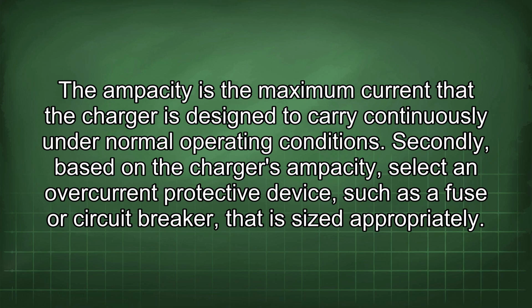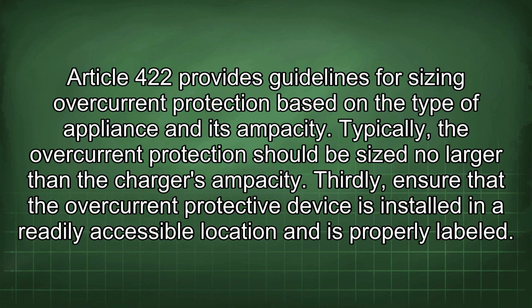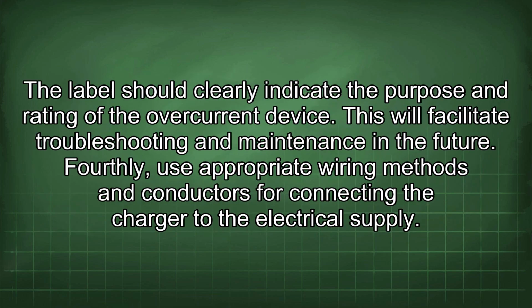Secondly, based on the charger's ampacity, select an overcurrent protective device such as a fuse or circuit breaker that is sized appropriately. Article 422 provides guidelines for sizing overcurrent protection based on the type of appliance and its ampacity. Typically, the overcurrent protection should be sized no larger than the charger's ampacity. Thirdly, ensure that the overcurrent protective device is installed in a readily accessible location and is properly labeled. The label should clearly indicate the purpose and rating of the overcurrent device. This will facilitate troubleshooting and maintenance in the future.